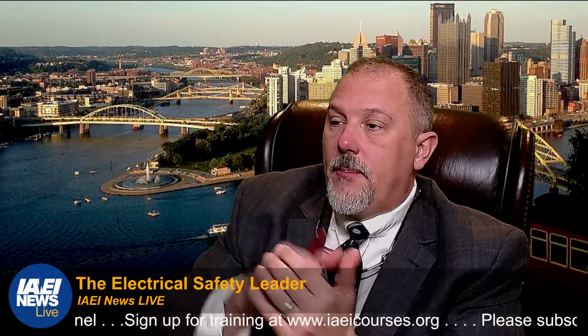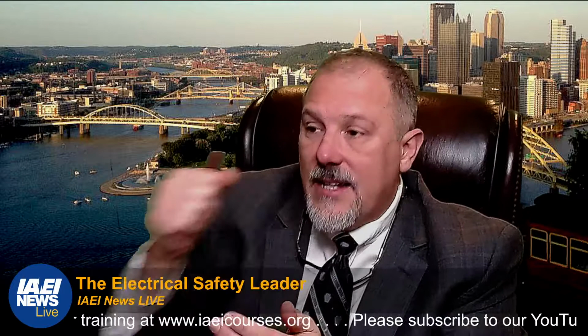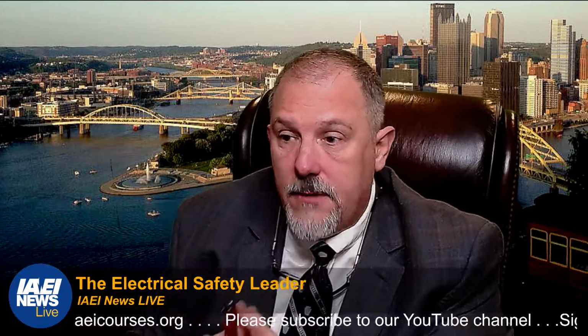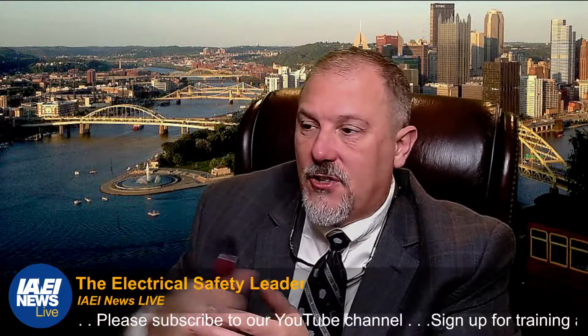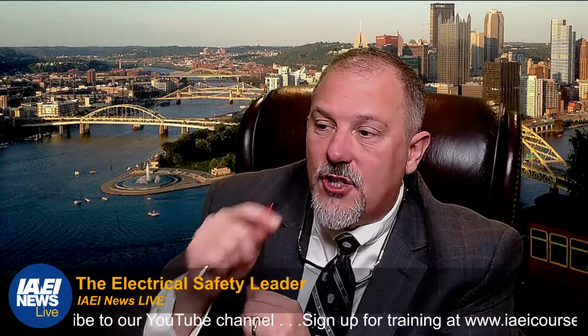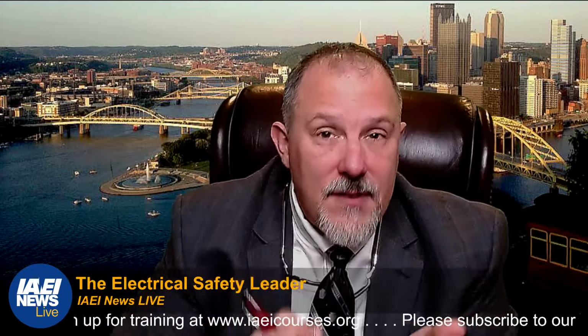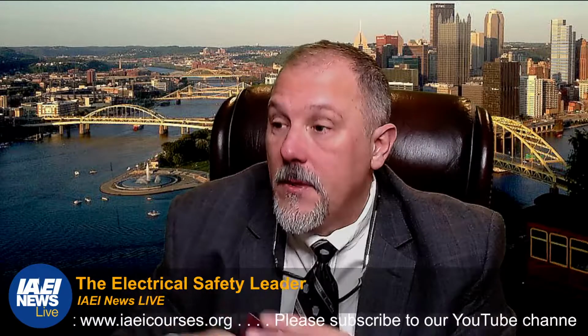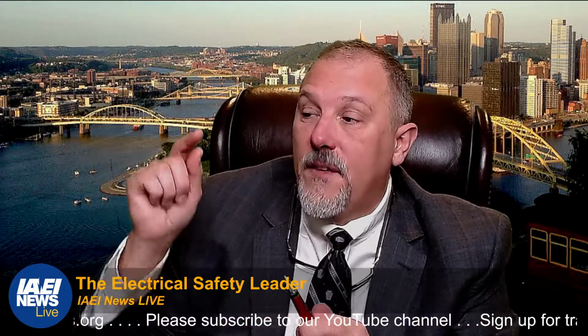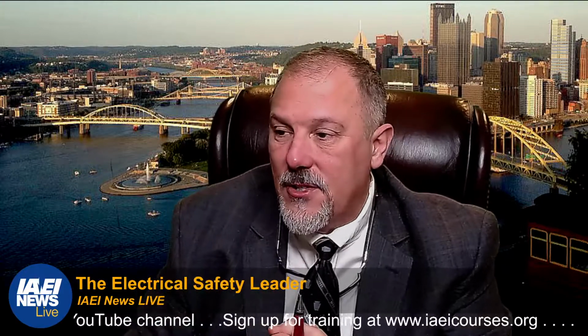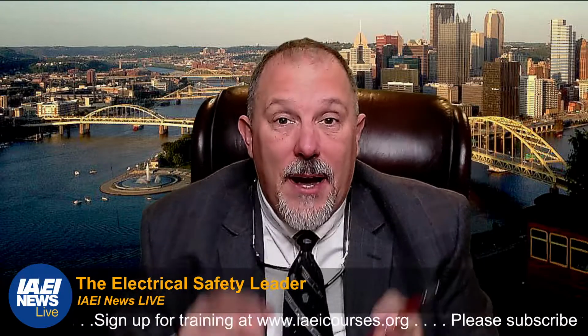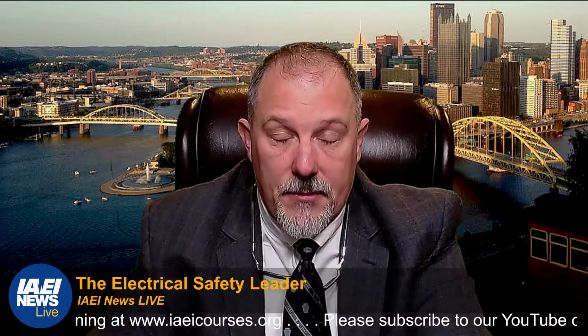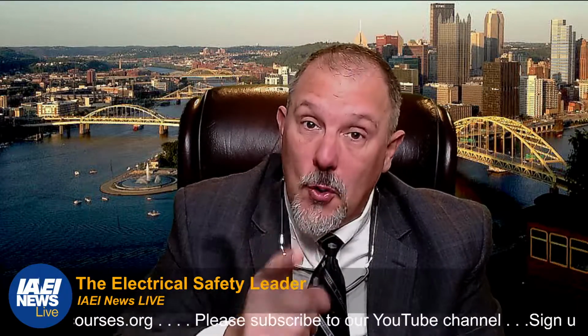5.8 says equipment cleaning: electrical equipment cleaning shall be part of the EMP. 5.8.1 says cleaning of the electrical equipment shall be performed in accordance with manufacturer's instructions. 5.8.2 says, in the absence of manufacturer's instructions, cleaning shall be performed in accordance with applicable industry best practices for the device being cleaned. And then cleaning personnel. No, you don't have to clean the personnel. It's the personnel who are doing the cleaning. Electrical equipment cleaning shall be performed by personnel who are familiar with the cleaning materials required and methodologies necessary for effective removal of contaminants, debris, and other materials that compromise the electrical equipment. You can do more harm trying to clean something than good if you don't know what you're doing. All right?